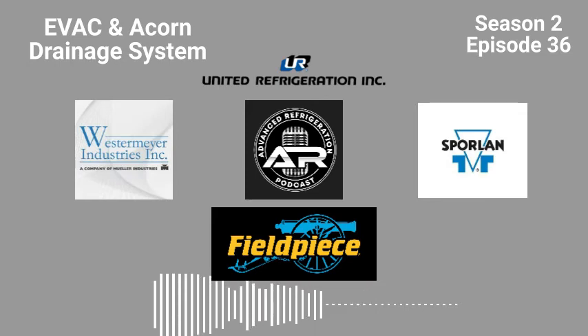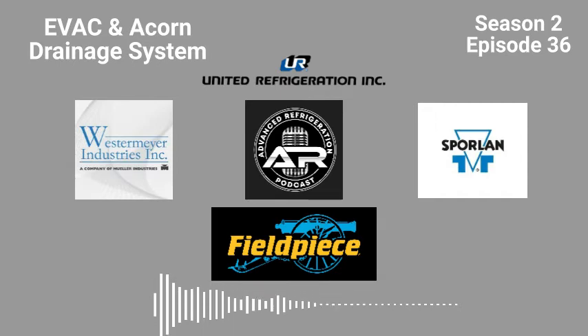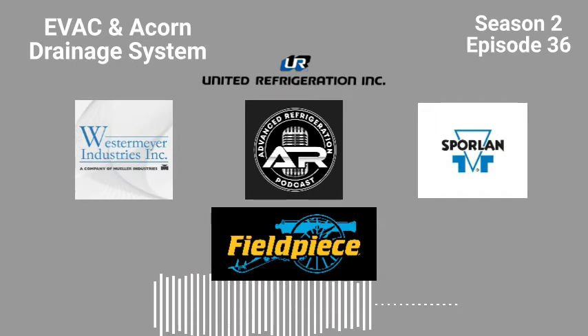Looks like Acorn's going to have to start making smaller fittings for that now. And the other problem we've had with EVAC and Acorn, which has only been brought up in a couple places, is that technically by plumbing code, you're supposed to have 1.5 times the drain diameter of an air gap going into the drain, which they consider the collector box the drain. Oh, wow. So if it's a 1-inch drain, it's supposed to be an inch and a half air gap. You cannot have that with that. Oh, okay. I got you. Because of the whole way the system's designed.